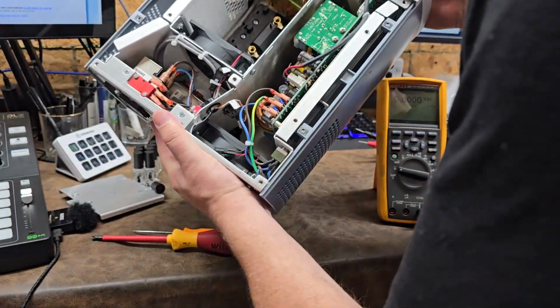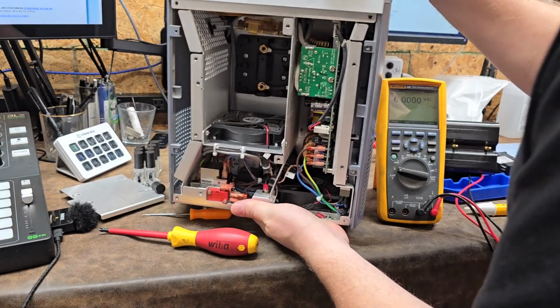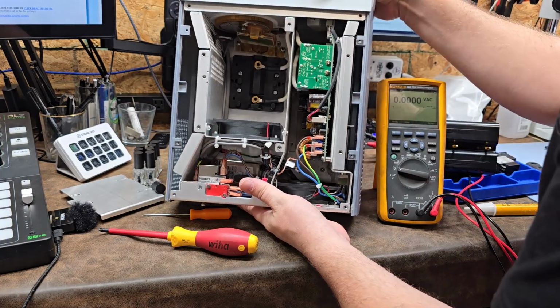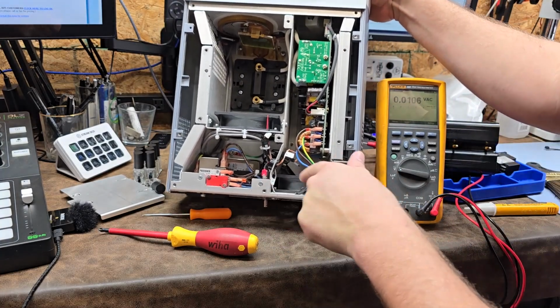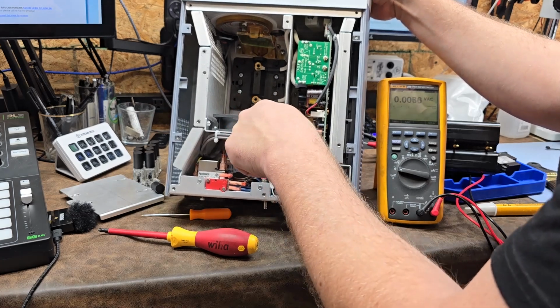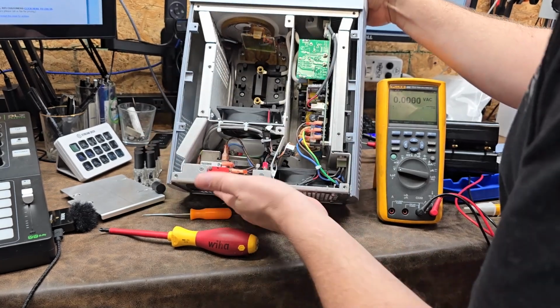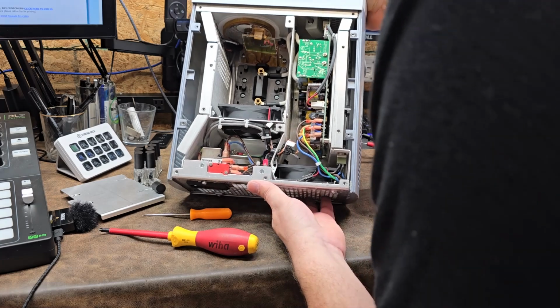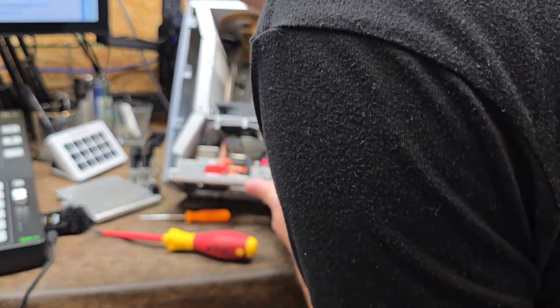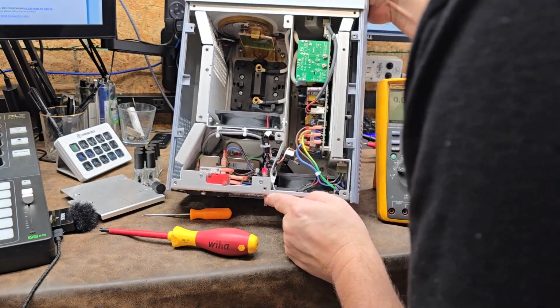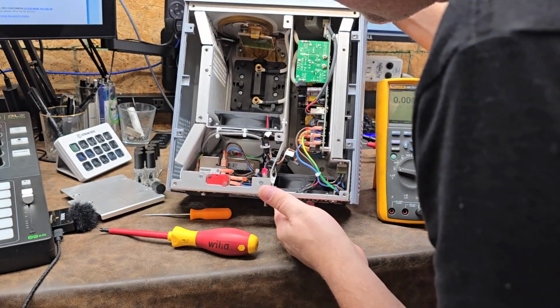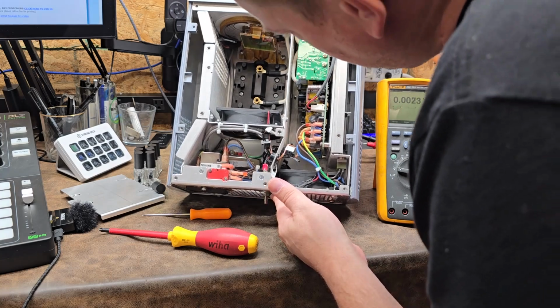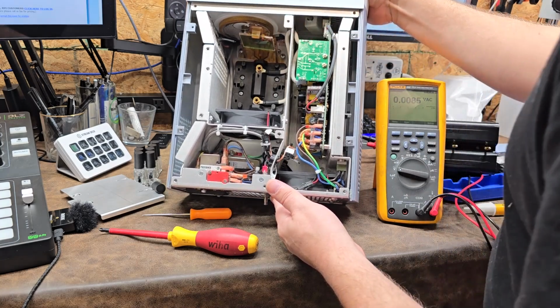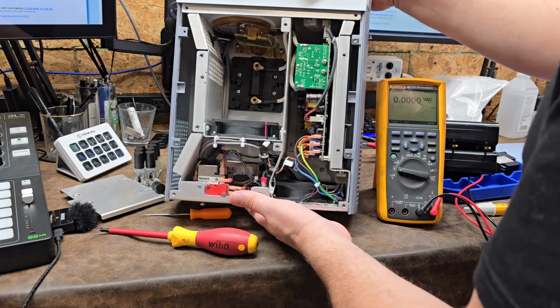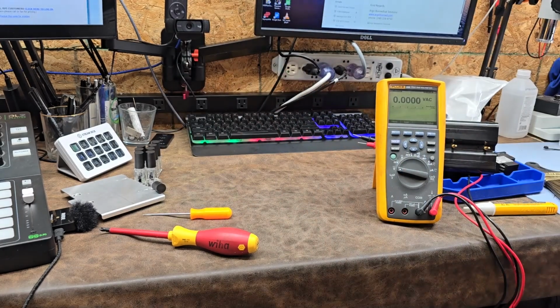So this guy here might be okay, it's a little bit dirty. See the fan inside? Those are the kind of things that need to be cleaned with the PM — the exhaust fan and the cooling fan for the bulb have to be cleaned, and any dust bunnies caught on the back grill, definitely recommended. I don't see any problems with the silicone wiring, because sometimes there's discoloration and insulation problems. Looks like it's okay, so it's not shorting to ground — otherwise it would have popped that fuse.